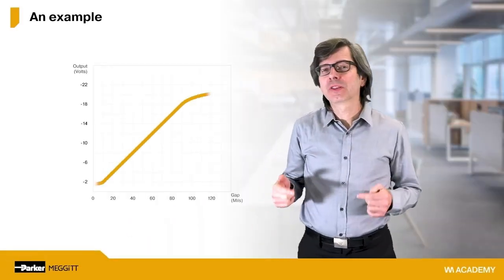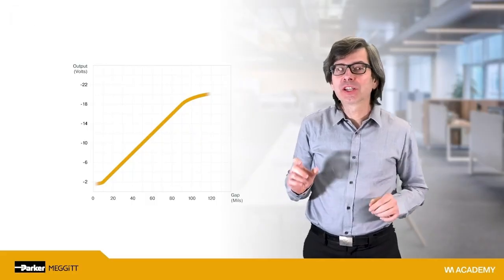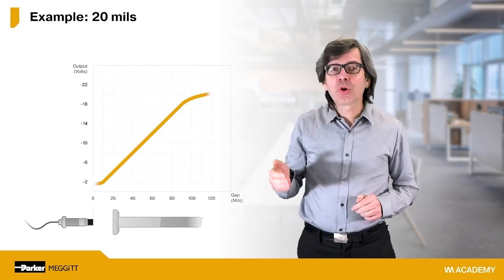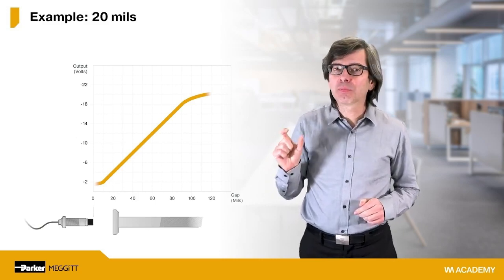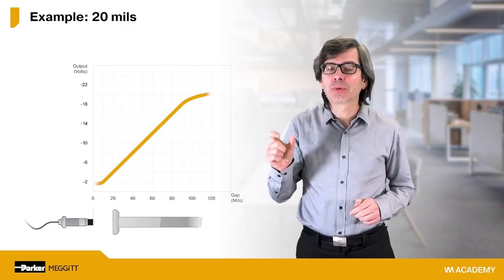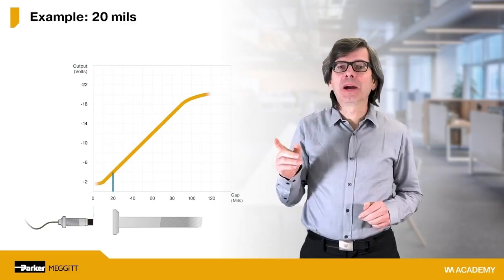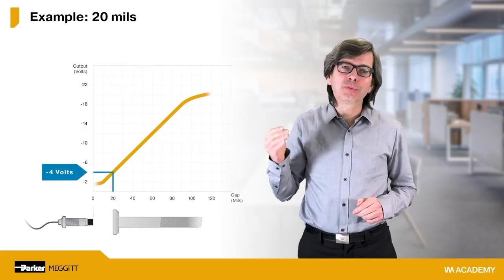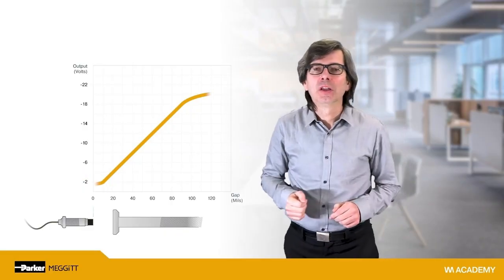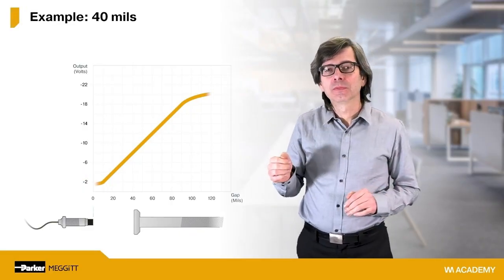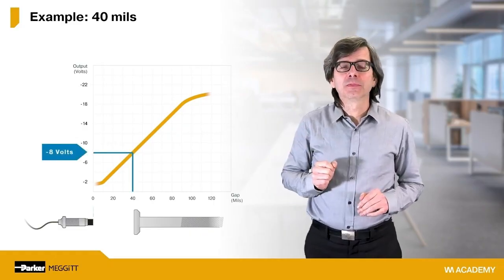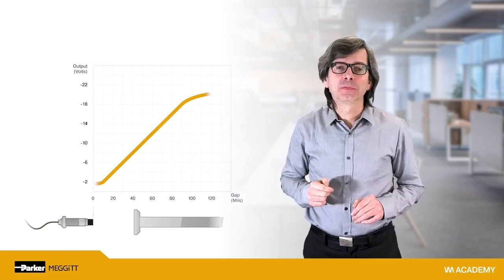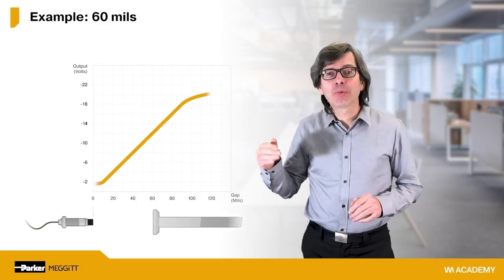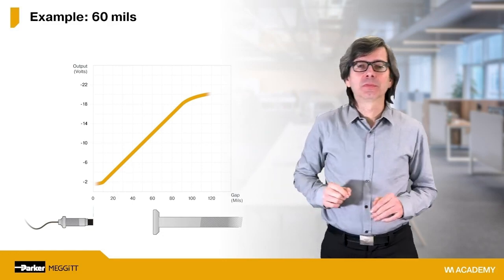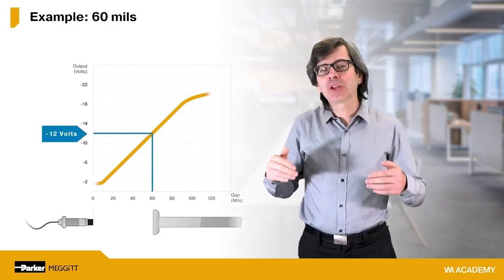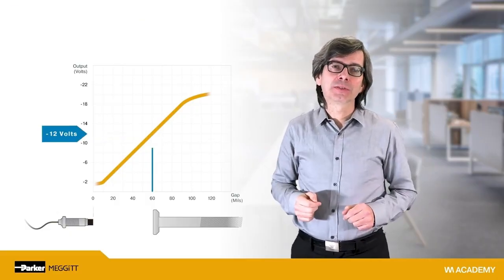To help reinforce your understanding of probe gap and voltage output, this animation will help. We start with the probe observing a target where the target is placed 20 mils from the face of the probe. As can be seen by the solid blue line, this gap results in an output of minus 4 volts. Now let's increase the gap to 40 mils. And notice that the voltage becomes larger. It is now minus 8 volts. We will now increase the gap one more time, this time to 60 mils. And notice that the voltage again becomes larger. It is now minus 12 volts.